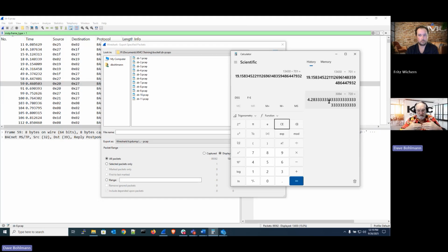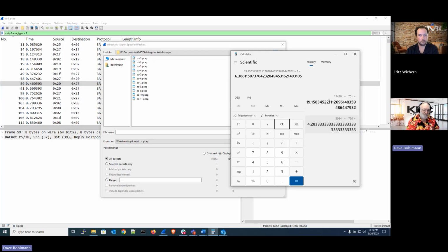Each point request has a request and a response, and most of them have a postponed, so it's almost like there are 3 messages for every point request. If I divide that by 3, there are more than 6 points being requested every second. And that's just a god awful lot.